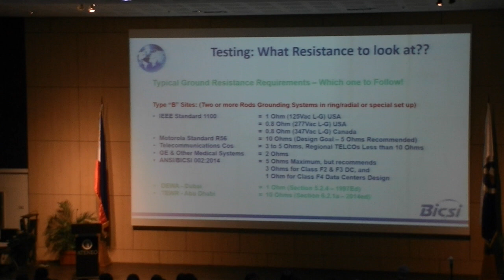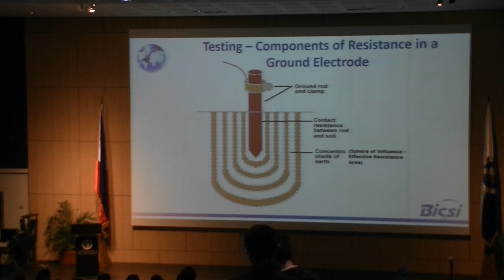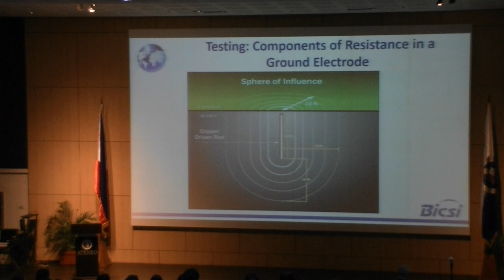Testing component for resistance, this is the component of the grounding system. They have what's called the concentric shell or sphere of influence. That's your rod within this area, that's your ohmic resistance reading. The rule is, your concentric area, if you have a 10 foot rod, 10 feet radius down to the surface, that's the concentric shell area or sphere of influence of your rod, if you use a rod, which is commonly used.